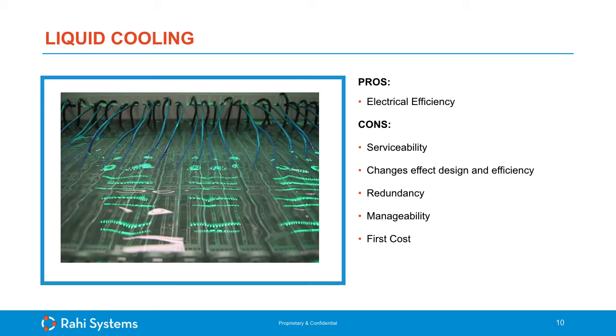So let's take a look at liquid cooling. Liquid cooling is a hot topic, pardon the pun. It's also a rapidly evolving technology in the marketplace. Arguably, it's one of the most efficient, as it is close coupled. It's about as close coupled as you can get to the IT load. There are many types of liquid cooling. There are dielectric chemical baths, as you see here. There are mineral baths, and servers are designed to drop right into the bath. There's also the maybe more traditional type, where refrigerant or water is piped into the server rack itself, more of a cooling to the chip. Many designs are coming out on the market.